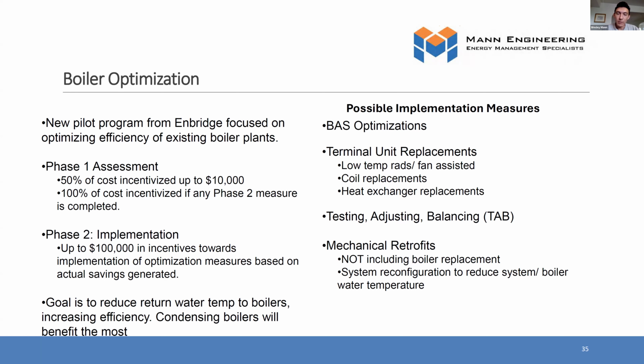And then, like I mentioned too, a lot of these buildings were designed around non-condensing boilers. So in a lot of cases, they're not meant to work at low temperatures. So there's potentially some mechanical retrofits that have to happen, piping modifications or changes to pump design, in order to make sure that the boiler system can work at low temperatures and optimize performance for the condensing boilers. So potentially, those could be implementation measures that could be covered by the incentive program.